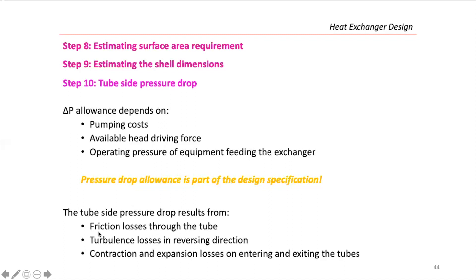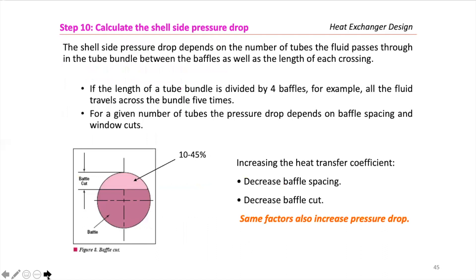The tube-side pressure drop results from friction losses through the tube, turbulence losses in reversing direction, and contraction and expansion losses entering and exiting the tubes. The shell-side pressure drop is equally important — when you are asked to design a heat exchanger, you are given the allowable pressure drop for both the tube side and the shell side, and you must accomplish both. The shell-side pressure drop depends on the number of tubes the fluid passes through between baffles and the length of each crossing. Decreasing baffle spacing or baffle cut can increase heat transfer but also increases pressure drop — there is a trade-off.